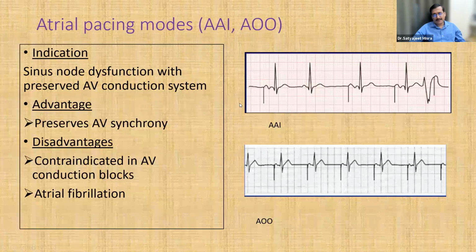One of the important things is once the pacing spike is given here, the pacemaker is going to wait for a predetermined time interval. So from here, you look at these boxes 1, 2, 3, 4. At the fourth box, it senses that there is an impulse here, and it doesn't deliver a pacing spike. Exactly, it will wait for the same time delay. So again, from here you see 1, 2, 3, 4. It waits for the same time delay, and here it senses that there is no P wave. Again, it will give a pacing spike.